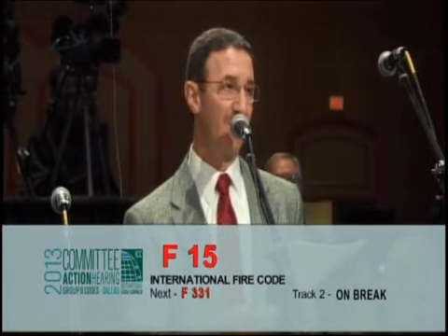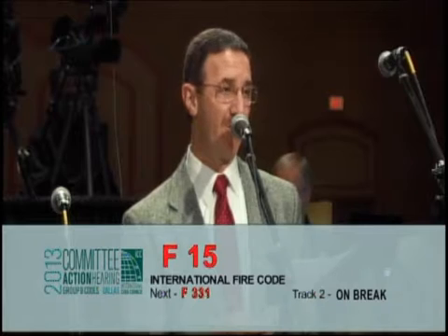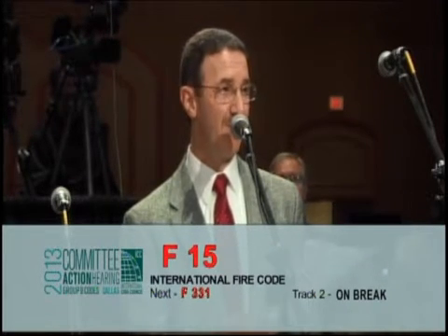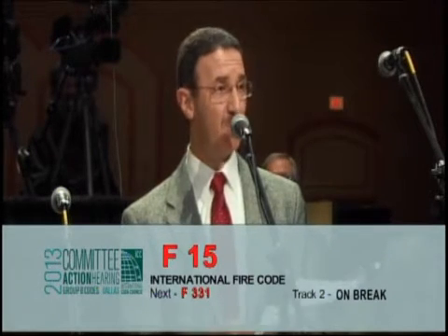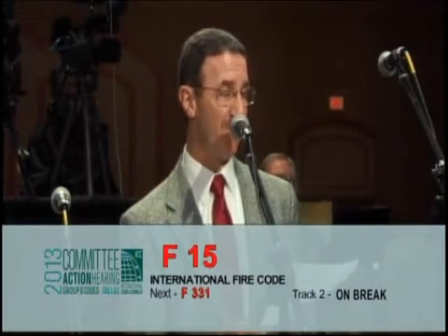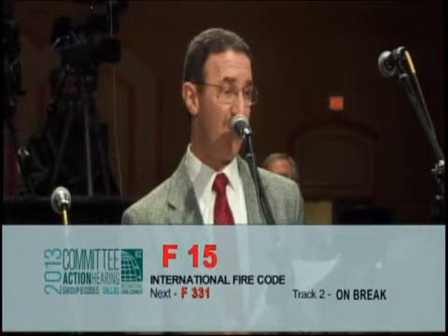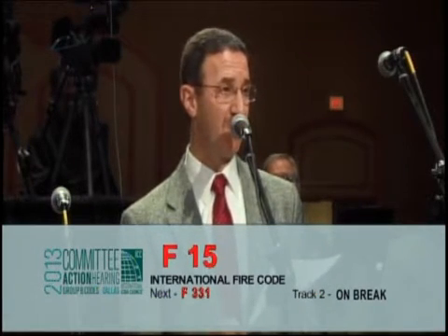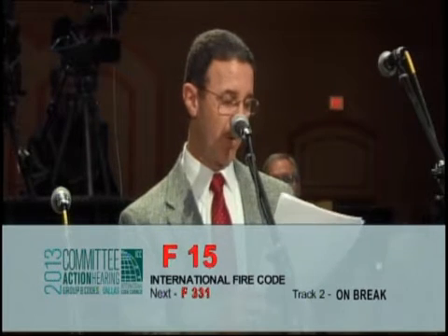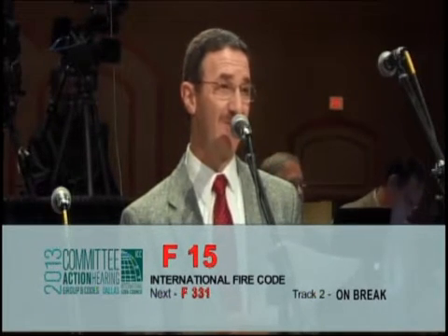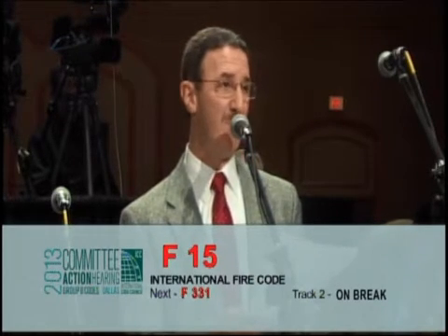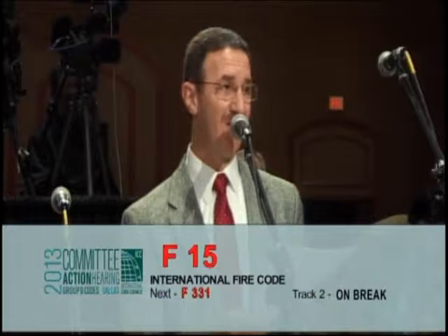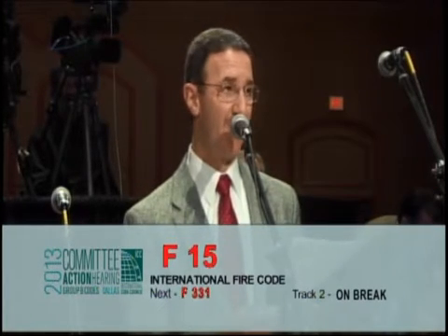You may judge that in some circumstances, a visual barrier, a bollard that's simply bolted to a concrete curb, is adequate to protect something in an area where the vehicle impact risk is low. On the other hand, you may have an area subject to truck impact where you don't want a bollard under 312.2, because based on the testing, I can absolutely assure you it will not handle it. I'll be publishing an article that has all this, and I've got neat side-by-side videos to demonstrate it, but it's all very thoroughly documented. This is a good change.